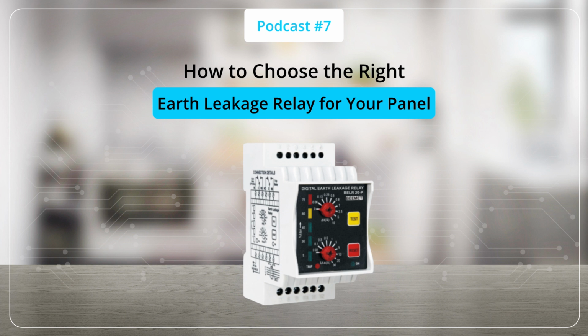Now let's discuss how Earth Leakage Relay connections are typically made. Proper installation is essential to ensure reliable operation and safety. The first step is connecting the auxiliary power supply. The supply is usually connected to the A1 and A2 terminals of the ELR. Most ELRs can operate with AC or DC voltages ranging from 110 to 240 volts.